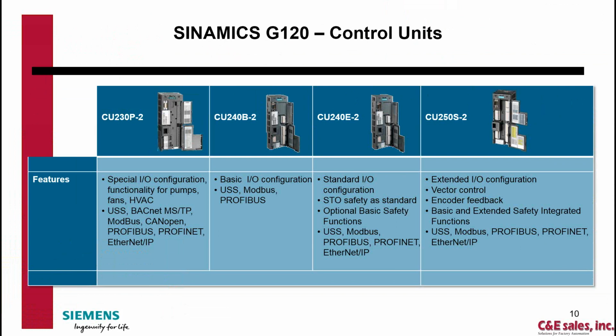Then here's some common control units. The CU230P-2 is traditionally a pump and fan control unit. You see some of these building type networks that it can do: BACnet, CANopen, Profibus, Profinet. Also, the CU240B-2 is going to be your basic 240 control unit. This is more of your traditional industrial applications. The B only comes with USS, Modbus or Profibus.